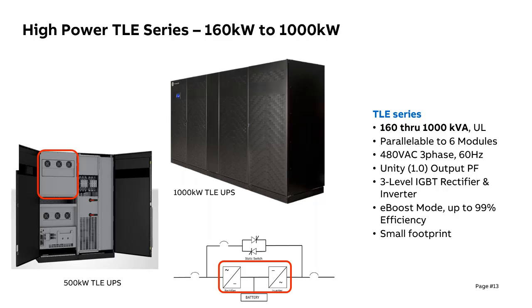As I said, not unique to ABB. This is true for any modern UPS. If you open the doors, that's what you would see. And just one comment before somebody wonders and asks: for the high power it is a 250 kW module, same as with the mid power, from 40 to 150. In this case, 160 to 1 megawatt. A 160 kW is essentially a 250 kW that has been told now you're 160. Mechanically, it's the same as a 250. In most cases, that's true for most manufacturers. It's just been told it's a derated version, and that's another, cheaper way of broadening your kVA product offering.